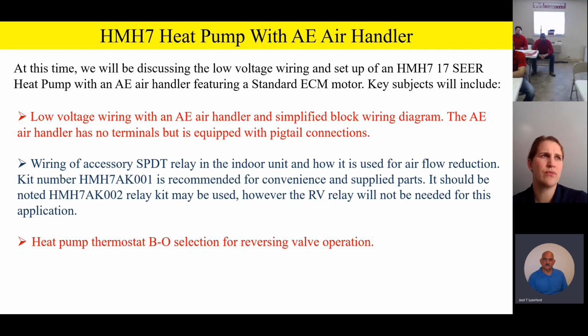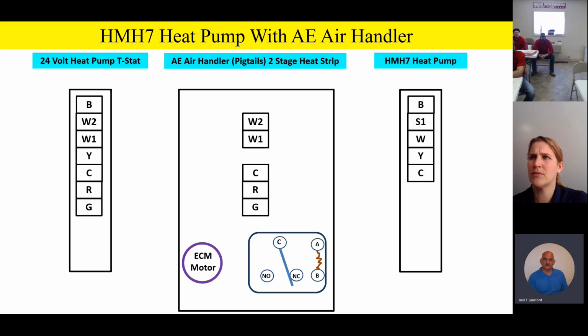We just have to keep in mind that we need a thermostat that's compatible for either B or O selection on the heat pump for reversing valve operation. So keep that in the back of your mind when you put these in, and as we go through some of the wiring diagrams and the block diagrams, we're going to utilize the B terminal to energize the reversing valve in the heating mode of operation. So with all that said, let's take a look at some of these block terminals.